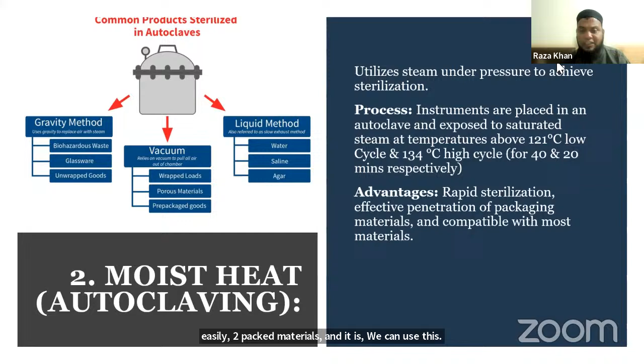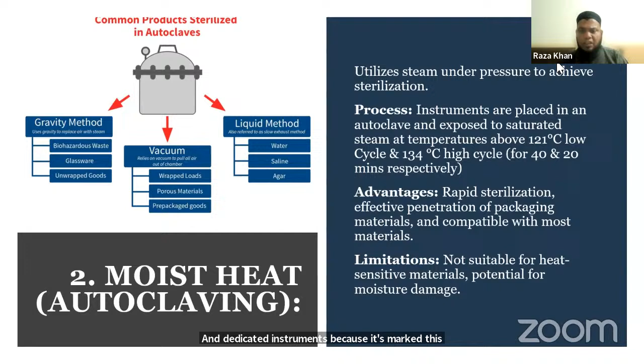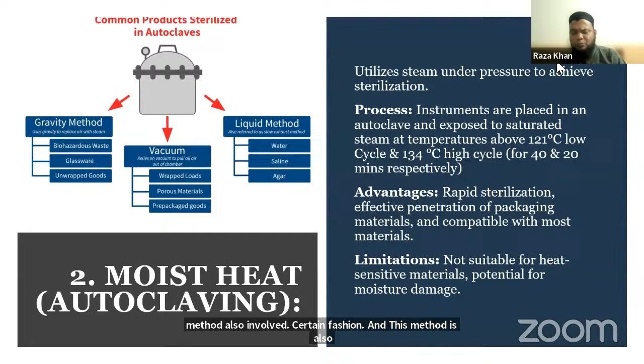In this method, the steam penetrates very easily through packed materials, and we can use it for package containers, instrument containers with filters, and for porous papers, micropore papers; heat passes through all these. This method also has some limitations: it is not suitable for heat-sensitive materials like rubber things and delicate instruments, because this method also involves certain pressure. And it is also not effective for items which are sensitive to moisture, like papers.